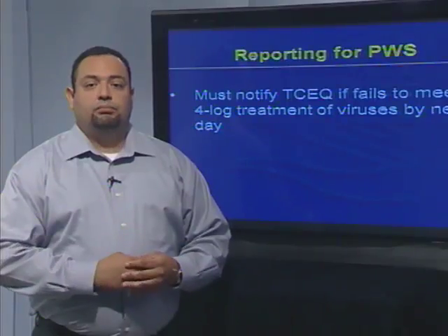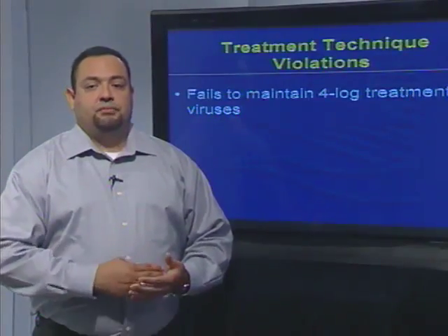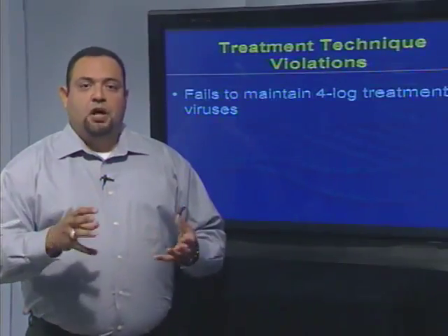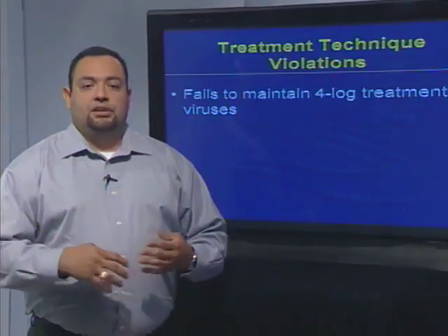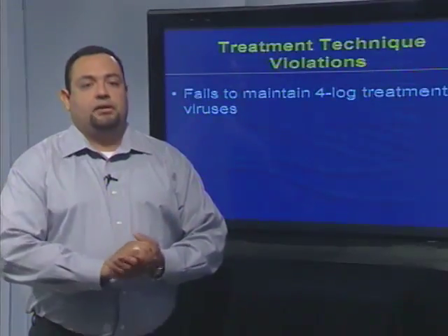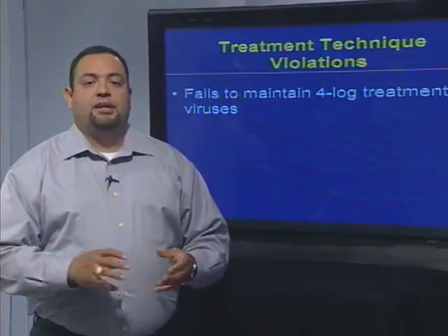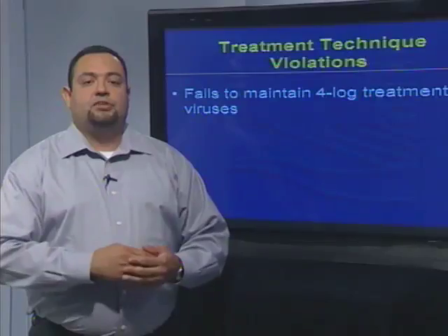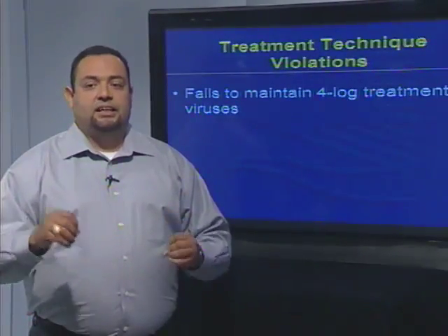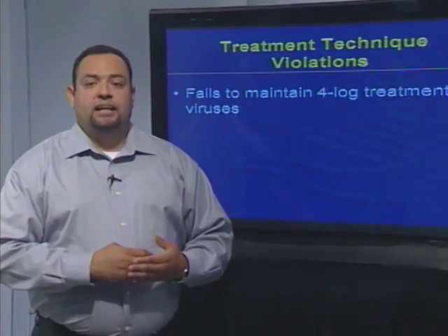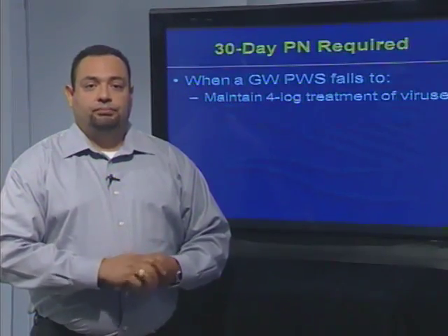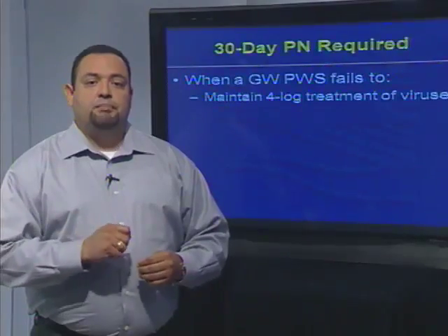So the next slide. Treatment technique violations, that's what I alluded to. If you fall below the MSR and you notify TCEQ and you still can't get that residual up within the 4 hour time frame, then you would obtain a treatment technique violation. But again, these are going to be very rare cases that water systems would get a treatment technique violation.